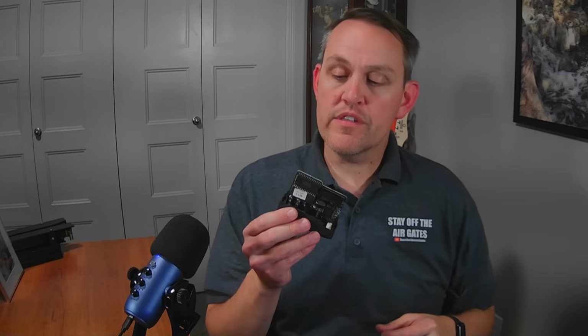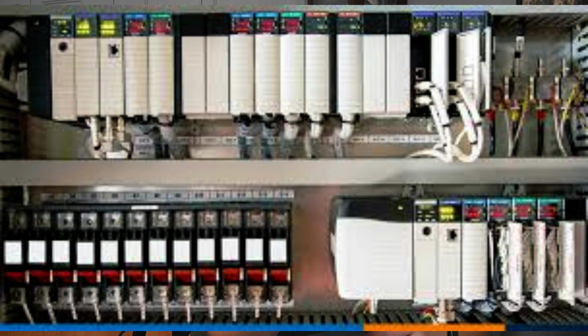And then a lot of programs use multiple ladders. Say once we've gotten to this part, go ahead and jump to this other ladder and start solving it there. And there are ways to manipulate that logic inside the program to make it run faster. Once you're done with startup, you could have a whole ladder that's just designated as startup, but once you're done with that startup process, you could simply not run that ladder anymore and save the time. Next, the program runs an internal diagnostic to make sure that the processor and all the input and output cards are running and working properly and that there are no problems with them.